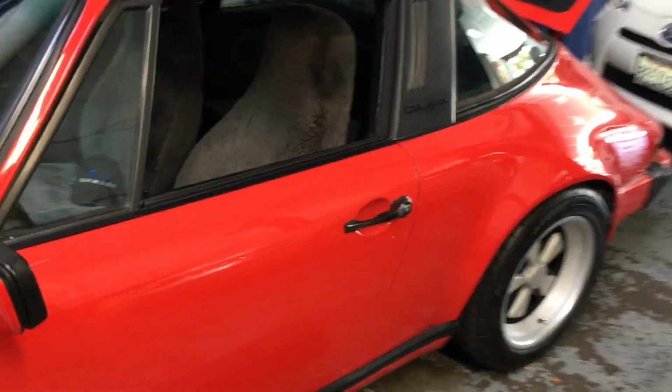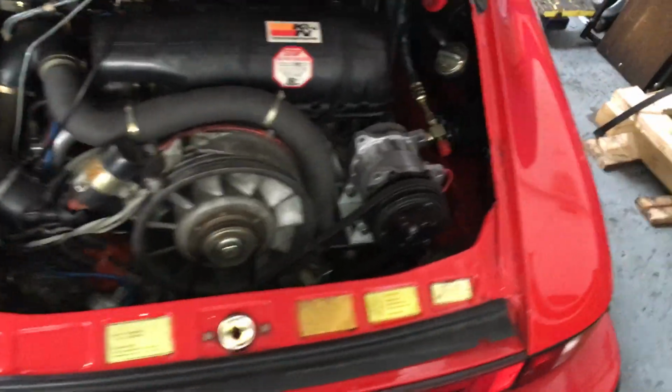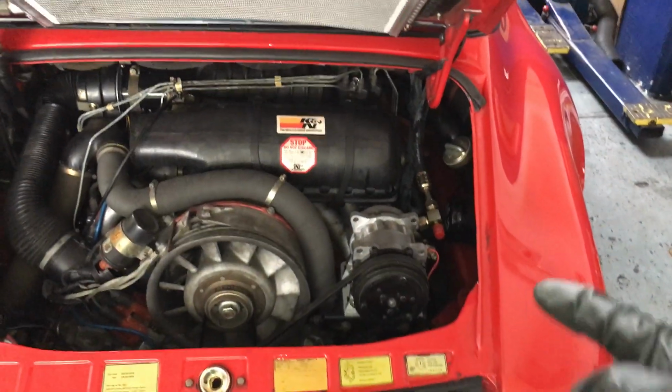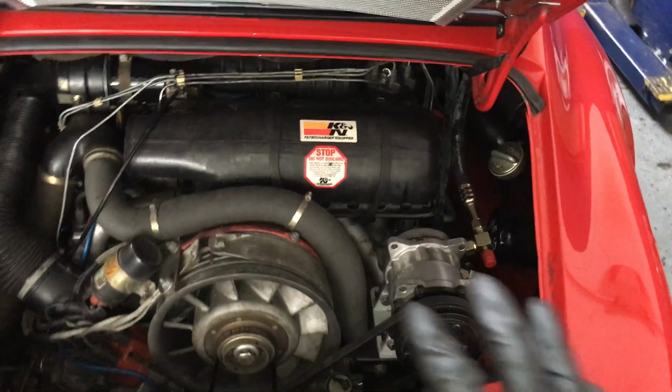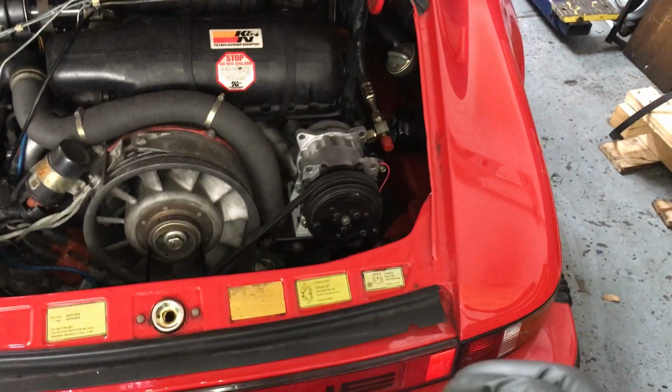That we can take care of next time, replacing the receiver dryer, and I'll leave it on my big vacuum pump overnight, and he should have a dry system. Plus on this situation, I'll be doing a triple purge and evacuate using nitrogen to help a little bit.